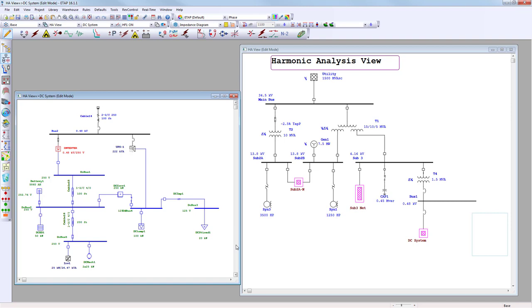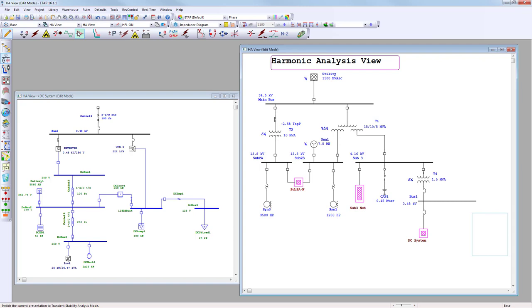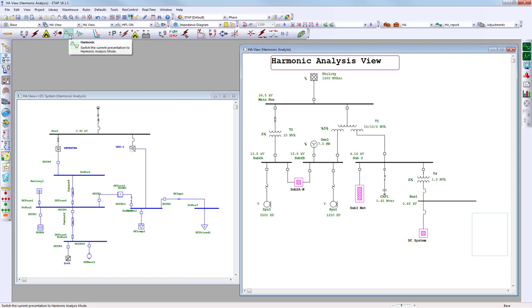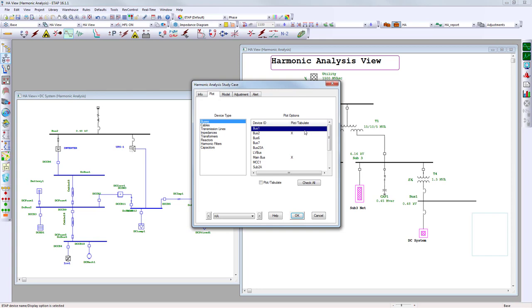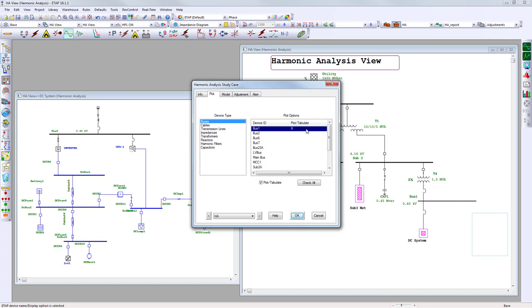Setting up most projects is straightforward. The rulebook already contains the limits for the point of common coupling — in this case 5% total harmonic distortion voltage and 3% total current distortion — as global settings. Next, switch over to harmonic analysis mode from the toolbar. Open the study case, which allows you to select which buses you want to display in results plots and on the one-line diagram.